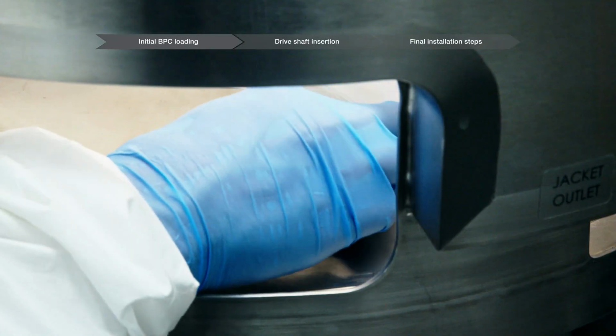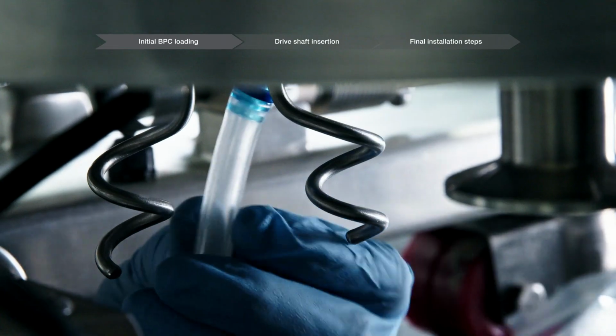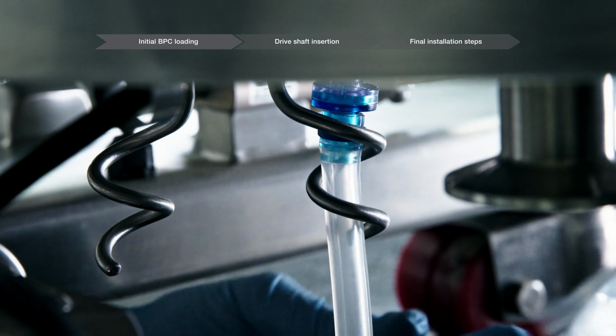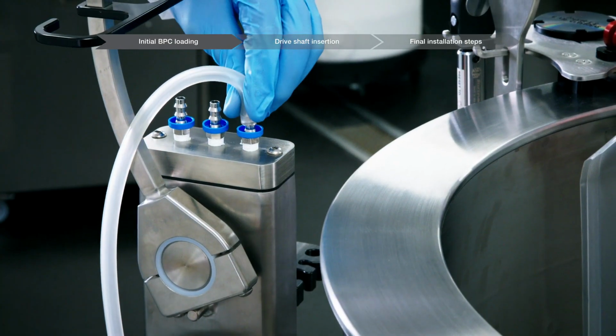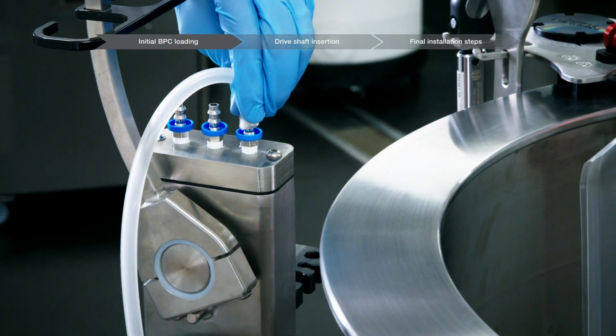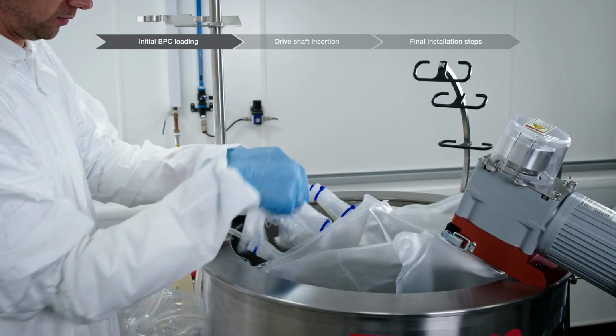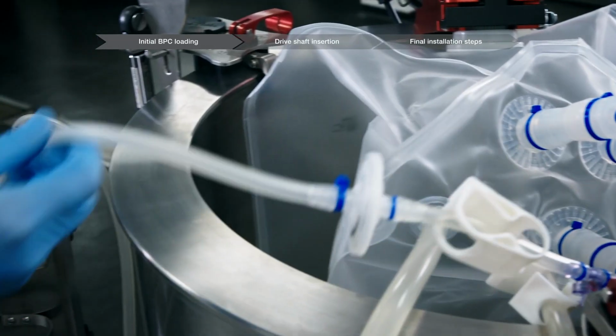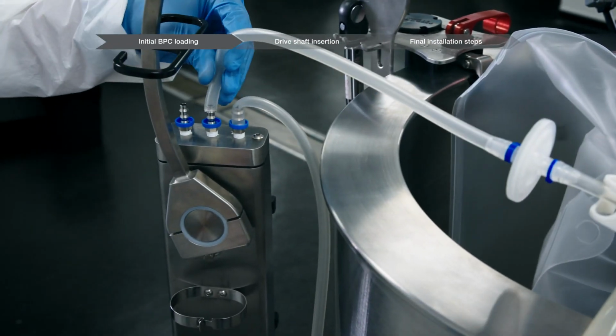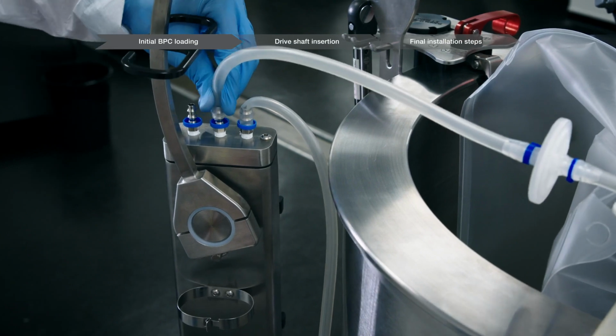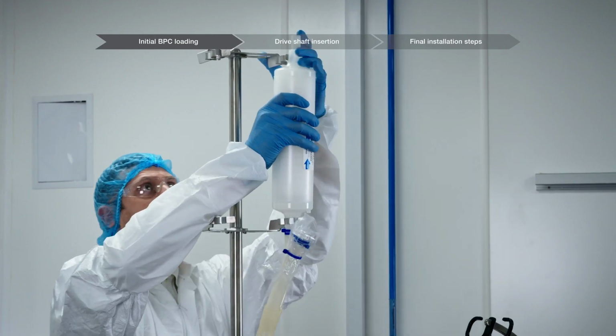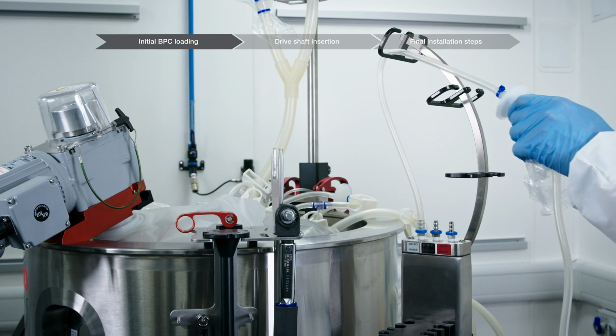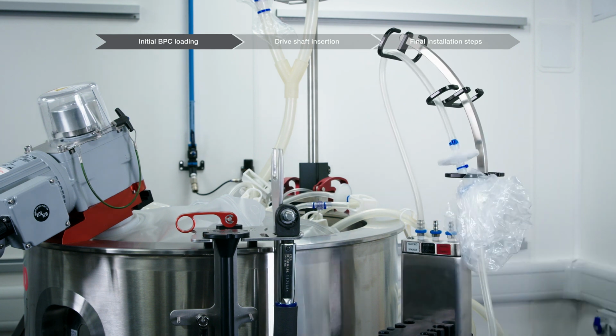Route the sparge lines through the bottom plate and loop them around the sparge line holder. If a cable management system is available, attach the lines to the appropriate inlet ports. Remove the bubble wrap and connect the incoming gas feed lines to both the overlay filter and the sparge filter. Install the vent filter and ensure that the filters are located above the maximum liquid level.